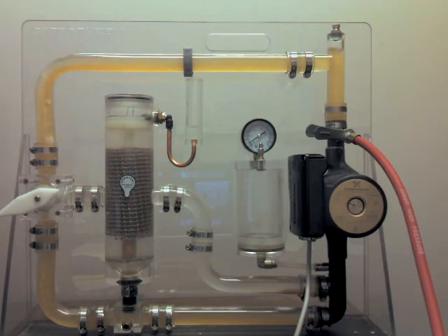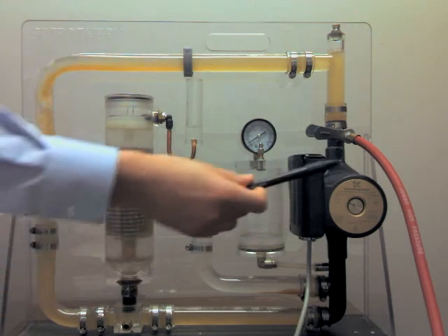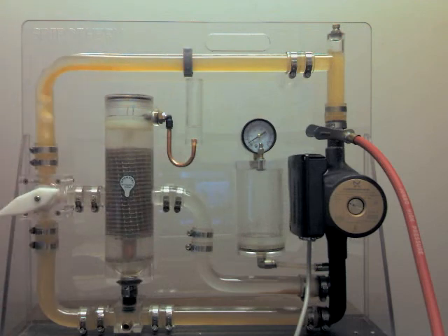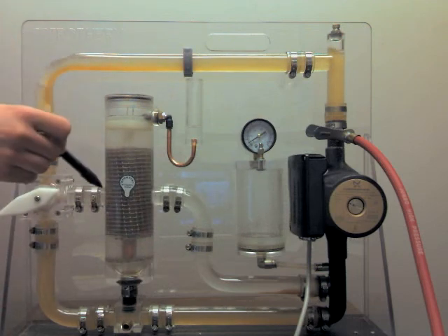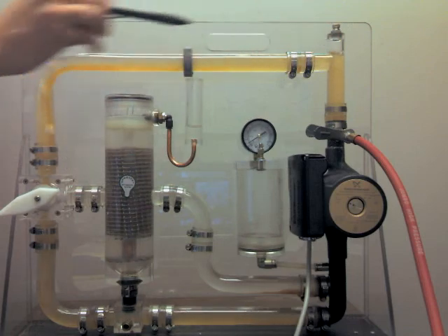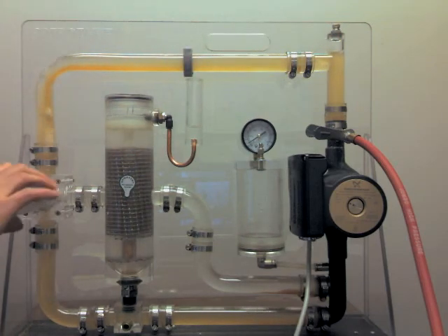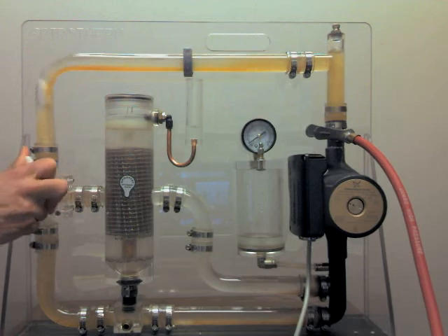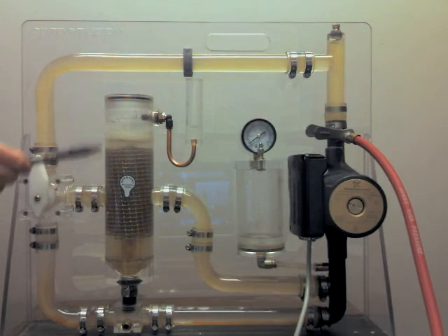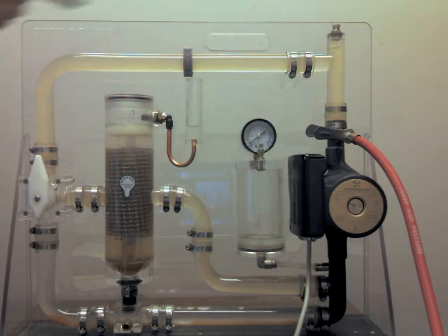Now dirt too is a very good insulator, just like the air, so it affects your heat transfer and your efficiencies. It definitely will trash equipment pretty quick. But as it's getting the air, just pay attention to this large air bubble in here too at the same time. Alright, so running it through, you see the air bubbles rising, the dirt particles are falling. And you see the air bubbles, pretty much just a little tiny bubble now. Most of it's been sucked out because of the water becoming absorptive. And that's how we're stopping the no heat calls.